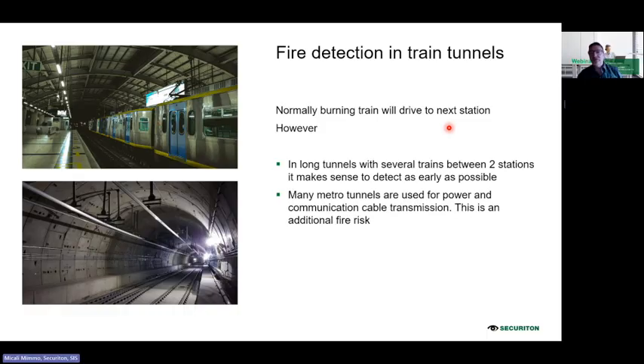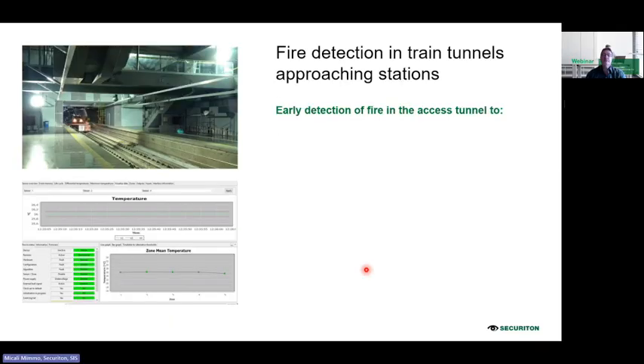And this communication is also important because normally the tunnel is also used for all the power cables we have. You see the power cables, normally they are installed on the side of the tunnel, some of them on the top. So this also causes a risk. It may also be a risk for a fire if there is some short circuit or some overheated cables, which may be the cause of a fire inside these tunnels.